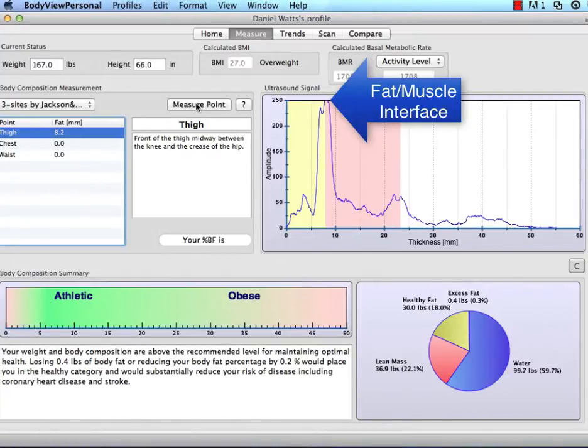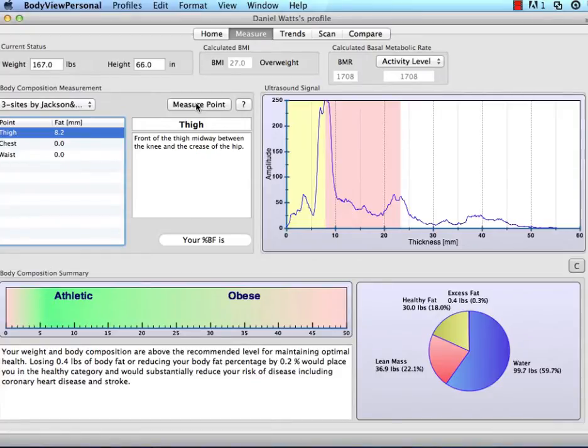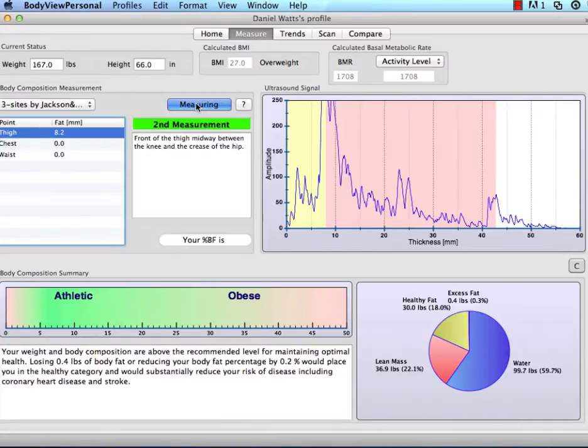Next, we'll demonstrate measuring without using the averaging technique. In this example, we'll press the button for a fraction of a second without moving the BodyMetrix device. The resulting measurement data graph shows an unaveraged signal with many fine, thin peaks representing various tissue structures.